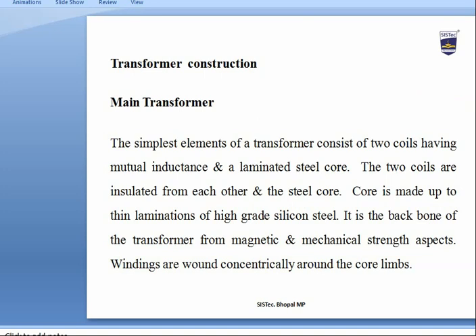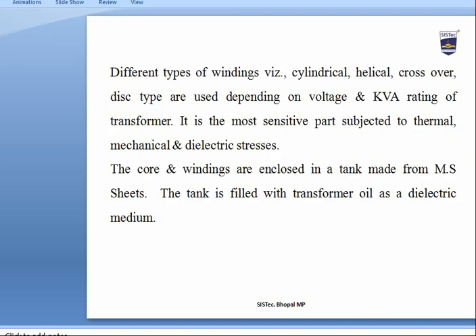The simplest element of a transformer consists of two coils having mutual inductance and a laminated steel core. The two coils are insulated from each other. The steel core is made of CRGO (cold rolled grain oriented) material — thin laminations of high-grade silicon steel. It is the backbone of the transformer for magnetic and mechanical strength. Windings are wound concentrically around the core limb; different types such as cylindrical, helical, crossover, and disc type are used depending on voltage and kVA rating.